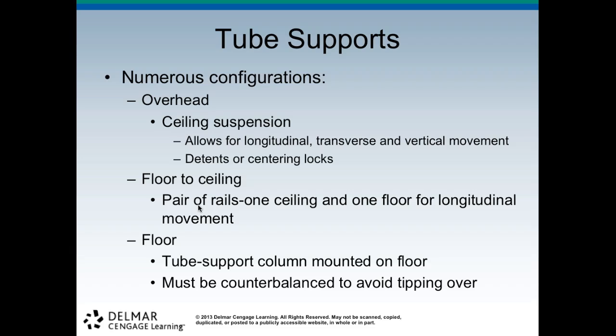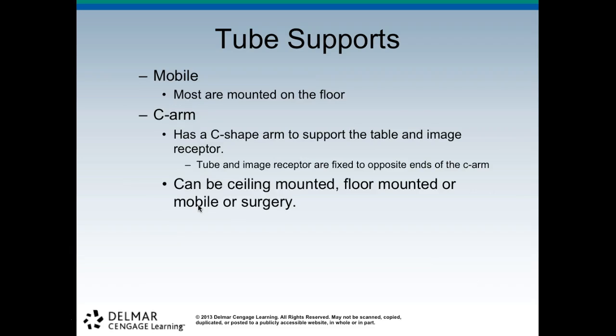So there's the overhead, which is the ceiling suspension. That's what we have. It allows for longitudinal, transverse, and vertical movement, and it detents and locks to the table and the wall Bucky. There's floor to ceiling, so it has a pair of rails, one on the ceiling and one on the floor, and it allows for longitudinal movement, so it only goes in one plane. And there's the floor, a tube support column mounted to the floor. The thing about those is it has to be counterbalanced or else it'll tip over, so you have to be careful.